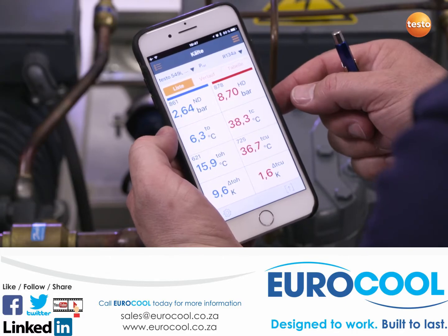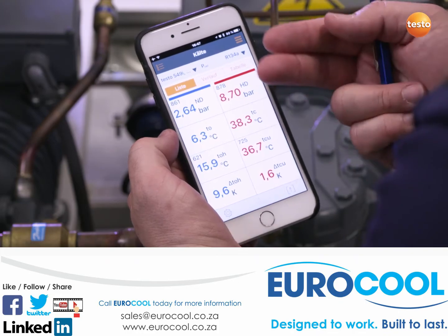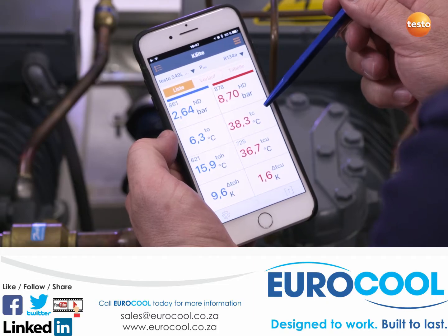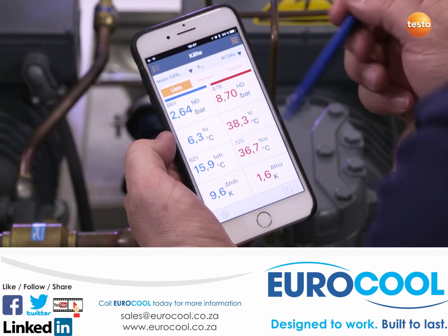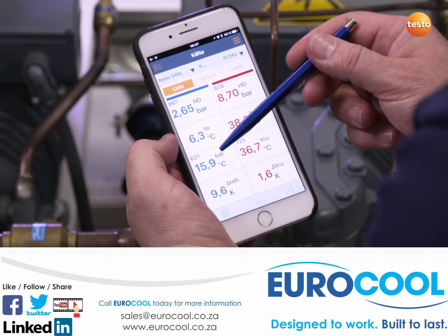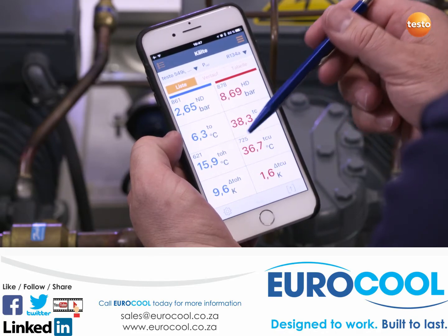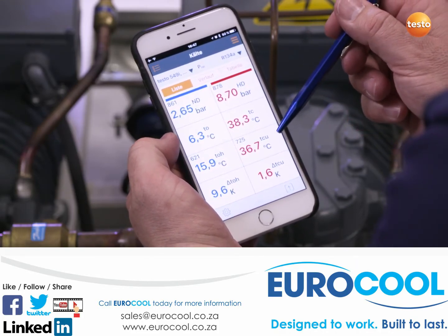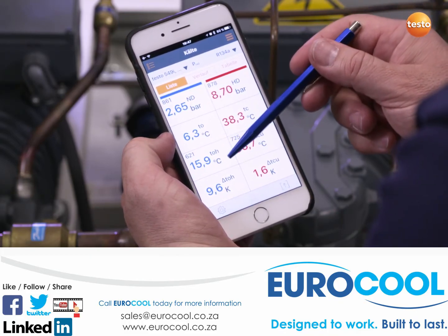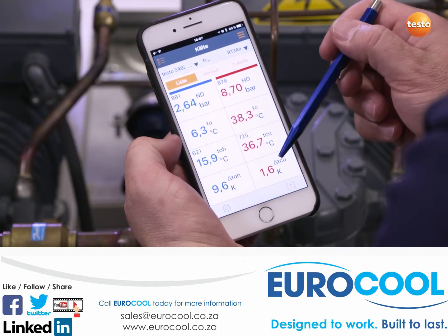The high pressure probe reports a pressure of 8.7 bar. The low pressure probe reports 2.6 bar. The instrument automatically converts the respective evaporation and condensation temperatures, which we are then able to read directly. Both temperature probes report a temperature of 15.9 degrees Celsius at the evaporator outlet and 36.7 degrees Celsius in the liquid line. The corresponding evaporator superheating is also generated automatically — in our case, 9.6 Kelvin is indicated — and a subcooling of the liquid line of 1.6 Kelvin.